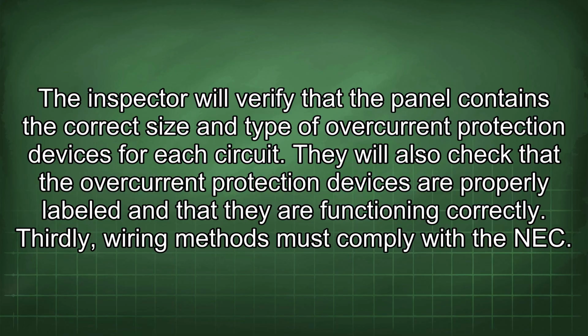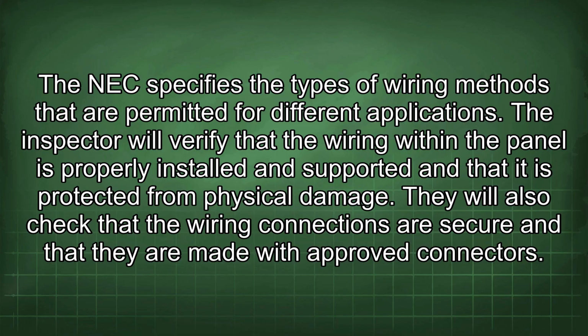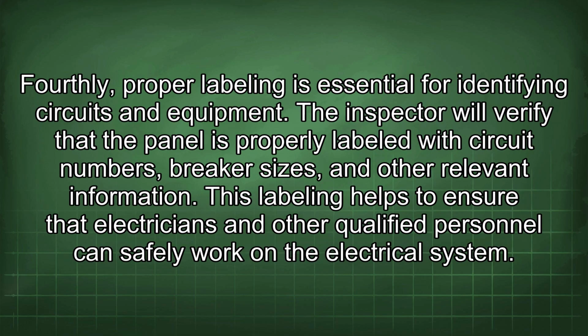Thirdly, wiring methods must comply with the NEC. The NEC specifies the types of wiring methods that are permitted for different applications. The inspector will verify that the wiring within the panel is properly installed and supported and that it is protected from physical damage. They will also check that the wiring connections are secure and that they are made with approved connectors. Fourthly, proper labeling is essential for identifying circuits and equipment.